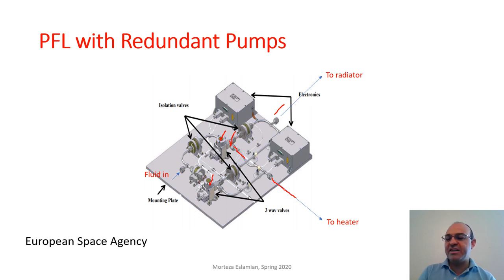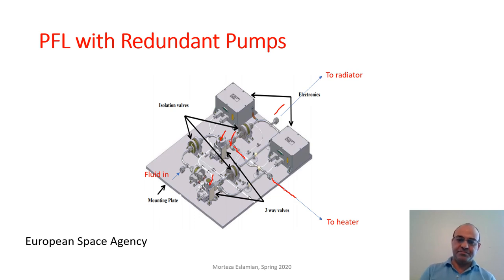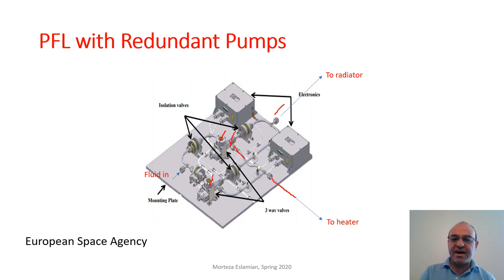However, if it's daytime or if there is a lot of heat to reject and the temperature is higher than the set point, the fluid will be directed toward the radiator to reject heat. Electronic boxes control this process — because this is an active system, the three-way valve, the pump itself, and the sensors are all powered, and electronics control the entire process.